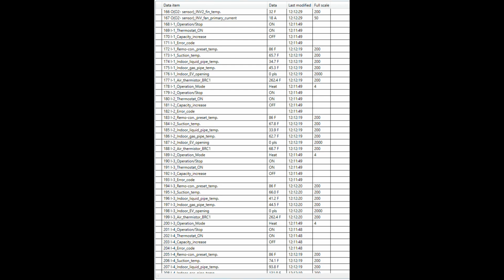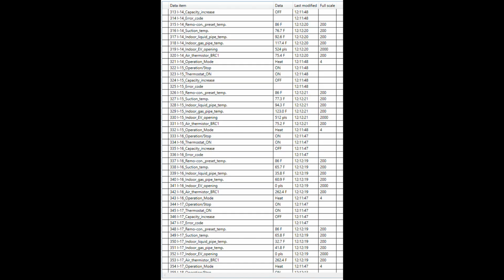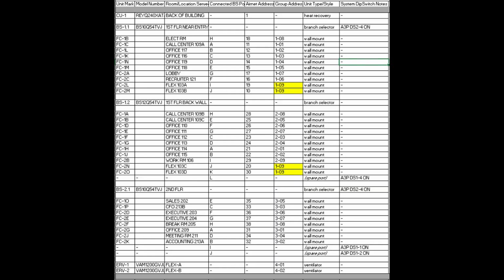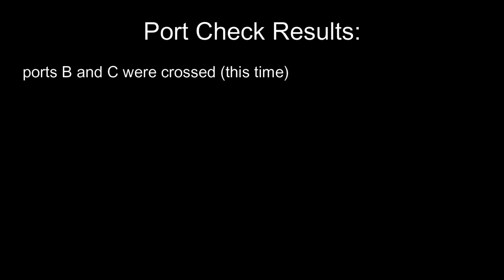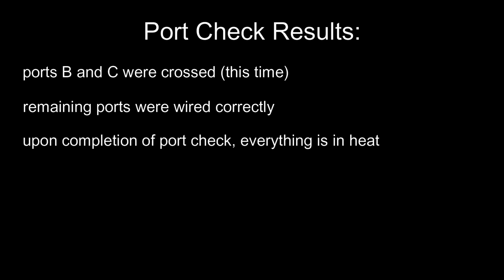Again, I don't want to constantly recycle power to the equipment. It takes extra time, which there is no need to waste if there are still other problems on the equipment. So to summarize, we had port B and port C crossed on one of the boxes. As we continue to work through each port of each box, everything looks good and we complete all the port checks smoothly and quickly.